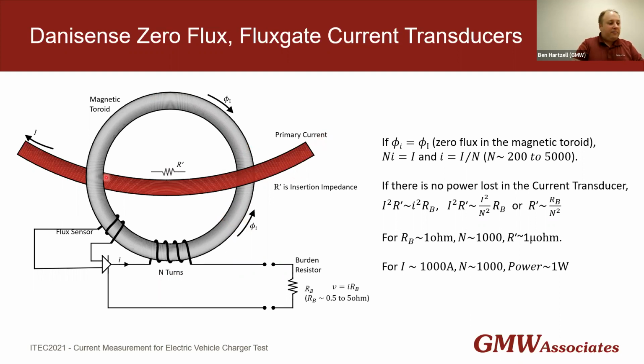The primary current I, flowing through a conductor, will generate a magnetic field, which then induces magnetic flux within the core. The flux is sensed by the flux sensor, which provides feedback to a secondary compensation coil, which has n number of turns, typically 200 to 5,000 turns. There's a small secondary current based on the feedback from the flux sensor times the number of turns to give a compensating magnetic flux in the core, which ultimately should result in zero total flux within the magnetic core. At DC and low frequency, the flux sensor consists of a flux gate, while at higher frequencies, it's instead a feedback winding to provide the feedback for the secondary current. In either case, the magnetic flux is being measured at sub-ppm levels.